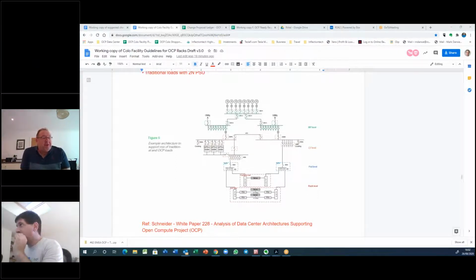But actually, you do raise a great point, because I've been sitting on the ACS calls, and people are starting to talk about 125 kilowatt cabs. Well, the largest IEC 309 connector you get is 125 amps, which is going to equate to something like 82 kilowatts. So what do you start doing for 125 kilowatt cabs? You either have multiple 125 amp connectors, or they become fixed installations. If they become fixed installations, there's a whole bag of other tests and certifications that will be required.